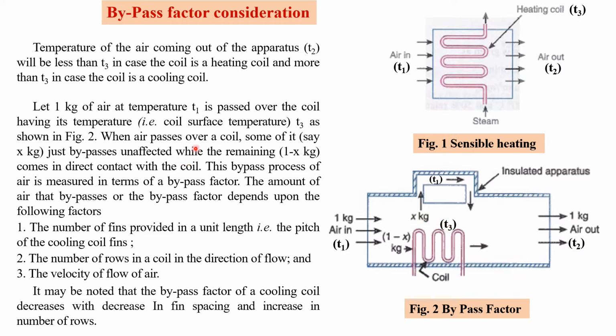So when air passes over a coil, some of it, say x kg, just bypasses unaffected, while the remaining 1 minus x kg comes in direct contact with the coil. So this bypass process of air is measured in terms of a bypass factor. The amount of air that bypasses, or the bypass factor, depends on the following factors: the number of fins provided in a unit length, that is the pitch of the cooling coil fins, the number of rows in a coil in the direction of flow, and the velocity of flow of air.